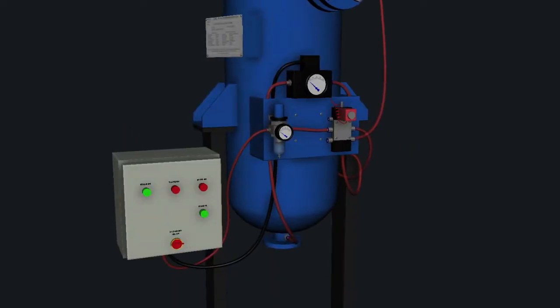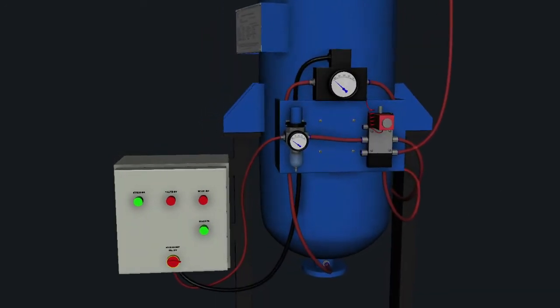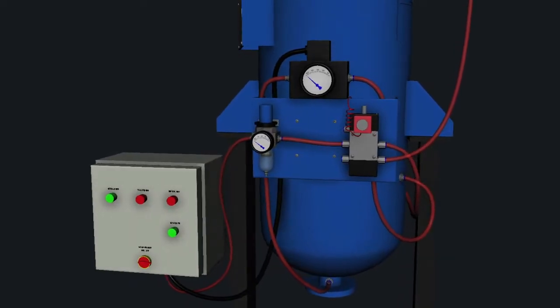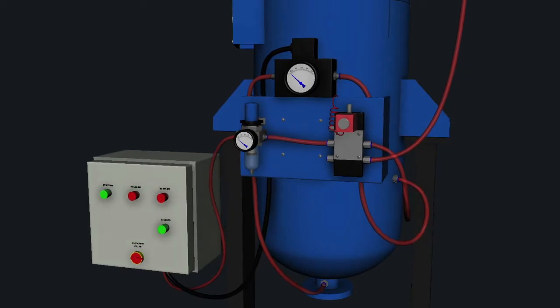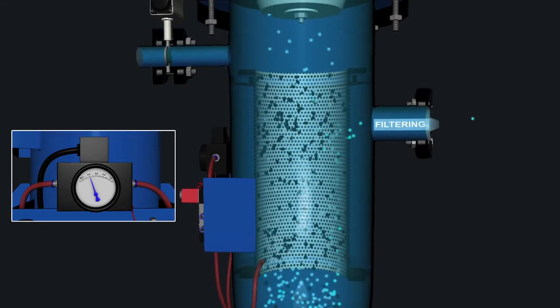ASC filters are equipped with a timer circuit and a differential pressure switch. The filter continues its operation until a preset timer value is reached or differential pressure value is reached. The filter enters into cleaning mode on trigger by either of these two inputs.